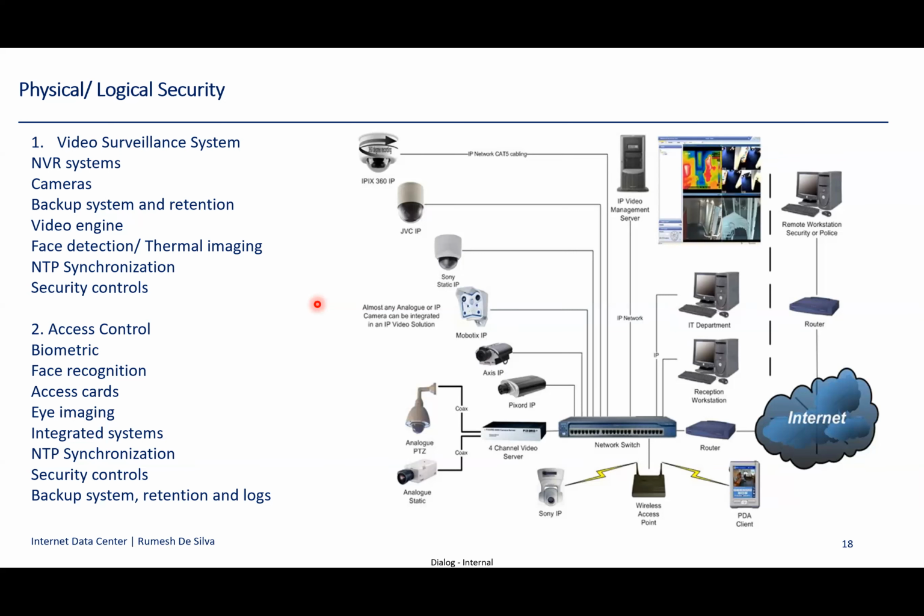And the NTP, yes, of course, network time protocol, is actually really important, because once you are working with a data center, the time of the access control system and the time of the CCTV should match each other. So once we are synchronizing the CCTV and biometric system times with a specific NTP server, then only we will be able to have good footage for some kind of investigation.